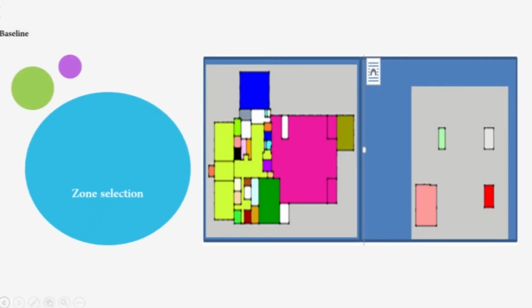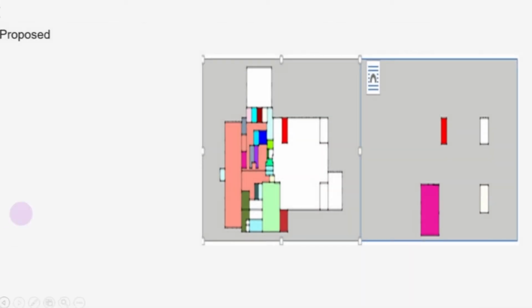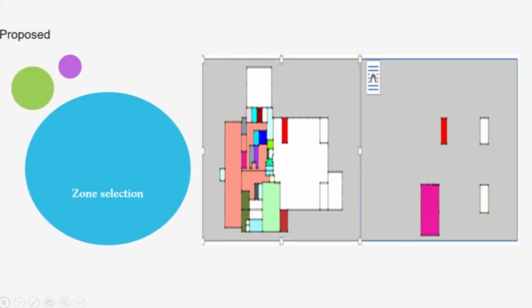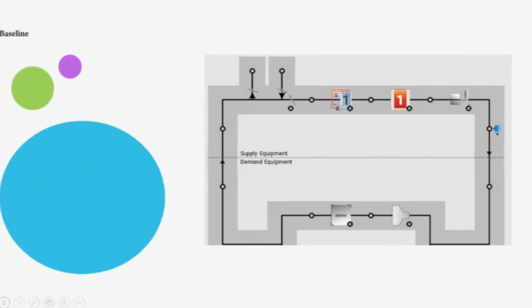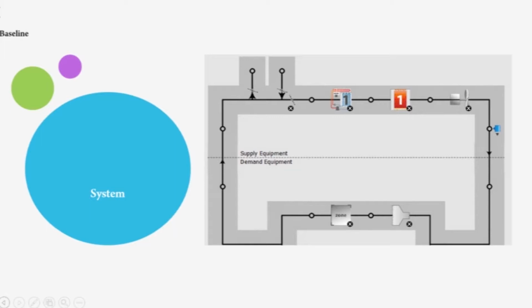For the building baseline, we use non-residential, three floors or fewer and smaller than 2,300 square meters for climate zone 8, using System 3, PSZ-AC, PGH single zone air conditioning. Efficiency for air-cooled air conditioners is based on the size category of each thermal zone. If the size category is smaller than 19 kilowatts, the efficiency is 3.81 SCOP. If bigger than 19 kilowatts, the efficiency is 3.20 SCOP. Furnace specification using Table 6.8.1-5, warm air furnace and combination warm air furnace or air conditioning unit, warm air duct furnace and unit heater.